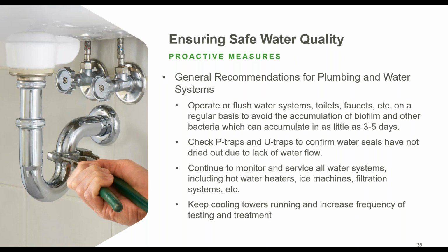Check P-traps and U-traps on all plumbing drains to confirm they are wet and that water seals have not dried out due to the lack of water flow. This can also lead to odors if not properly maintained. Continue to monitor and service all water systems, including hot water heaters, ice machines, filtration systems, etc. Now, regarding hot water distribution systems, ASHRAE recommends keeping these systems circulating and storing hot water at above 140 degrees Fahrenheit to avoid microbial growth within these systems. If the hot water recirculation system goes down for an extended duration, a high temperature flush may be required before going back online.